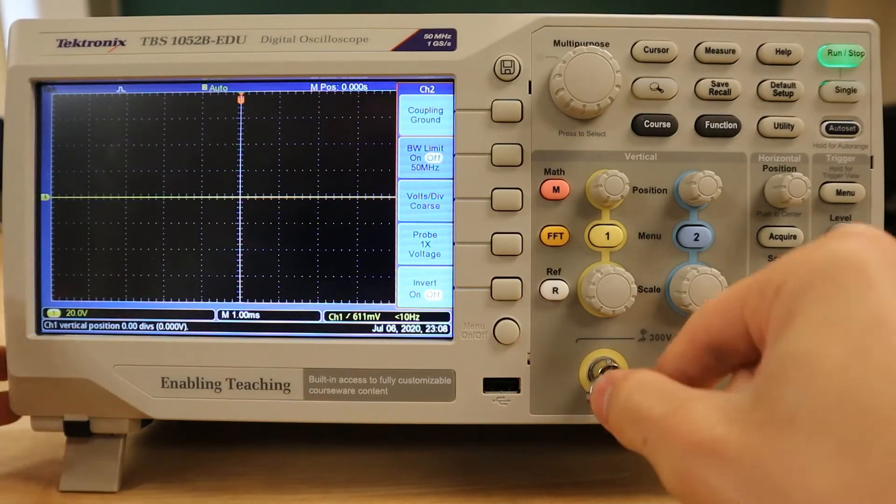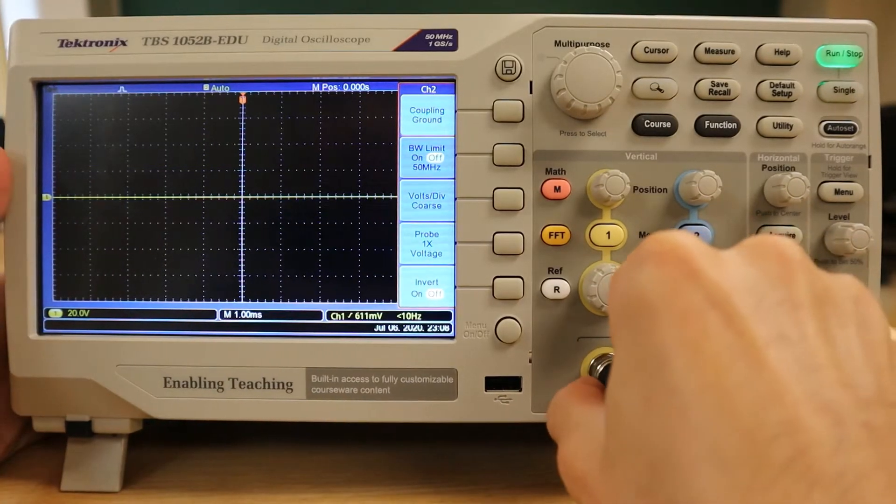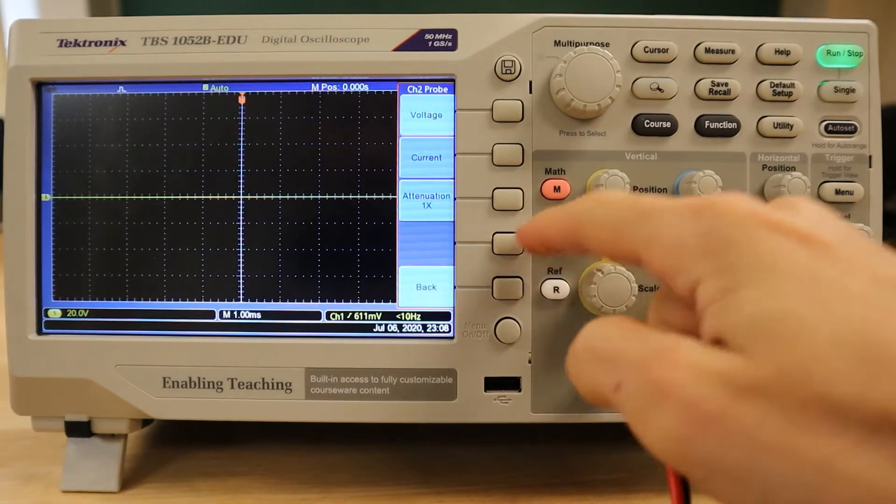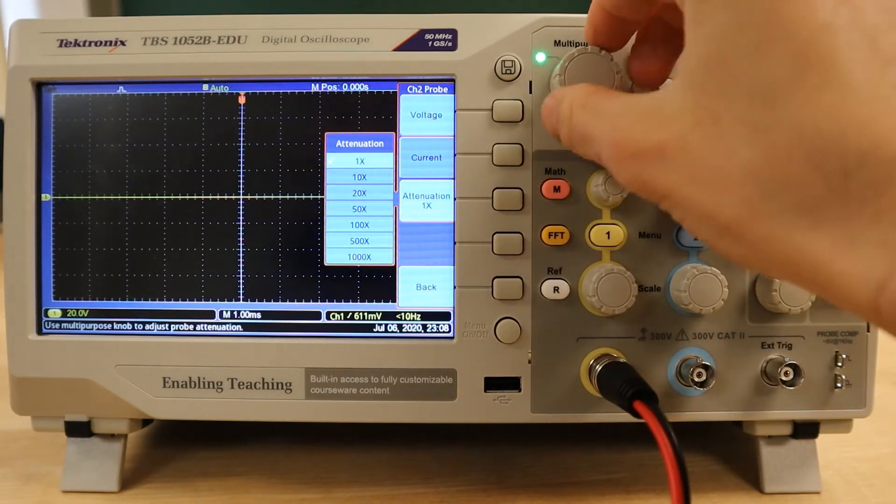Since we'll be connecting a BNC to banana cable, no attenuation factor is necessary, so we must make sure that the channel is set to 1x voltage magnification.